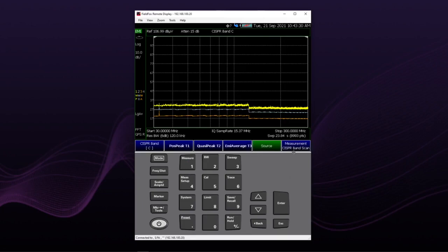So I would head back to measurement and leave it as such. I will not turn on the preamp. You would only want to turn that on if you're very sure of the power levels that you're measuring or expecting. Otherwise, keep the preamp off and do keep the attenuation levels.